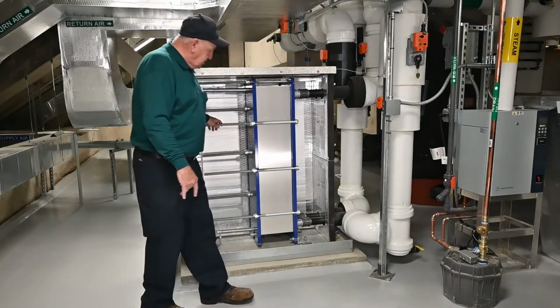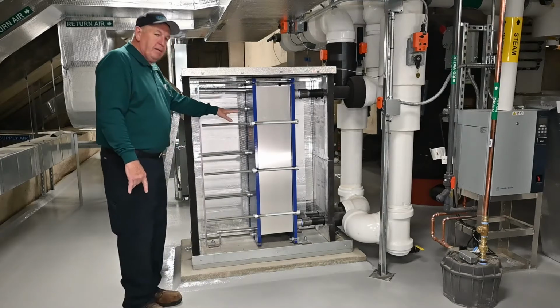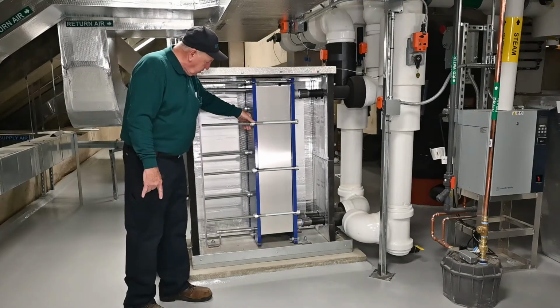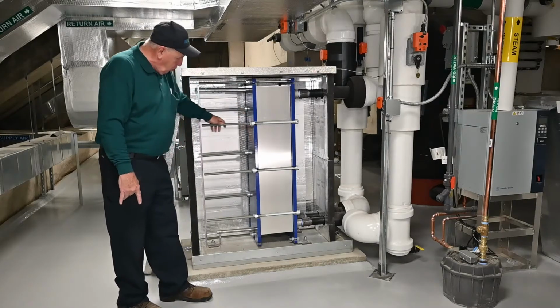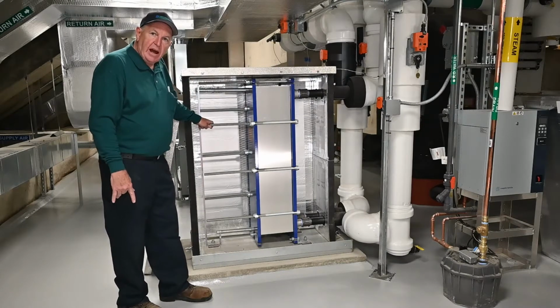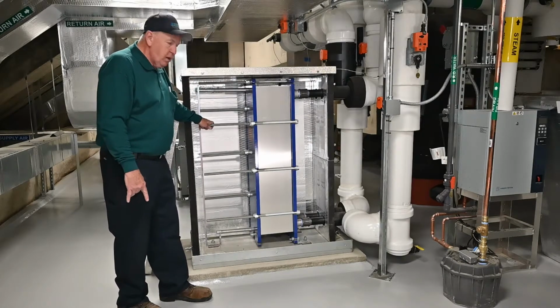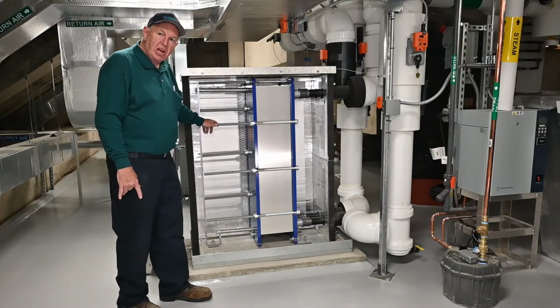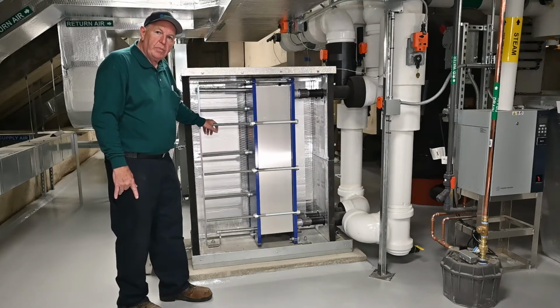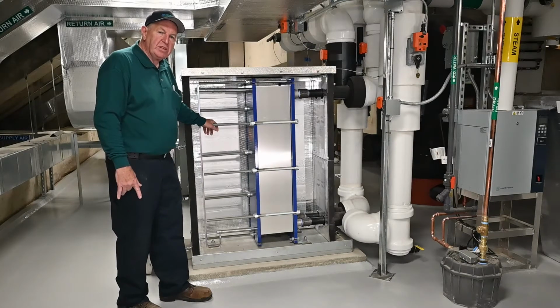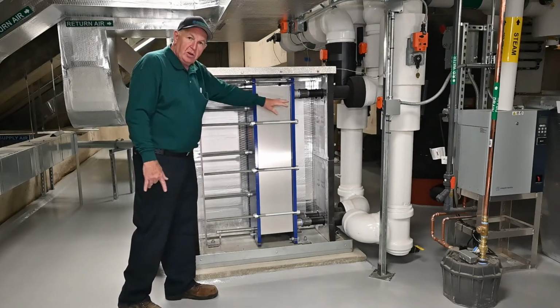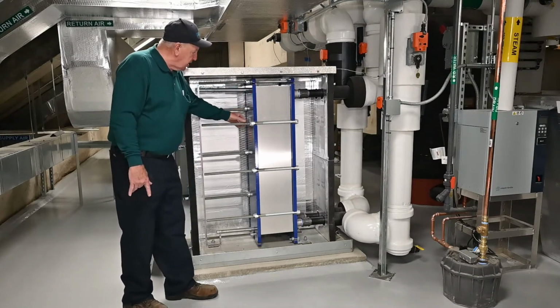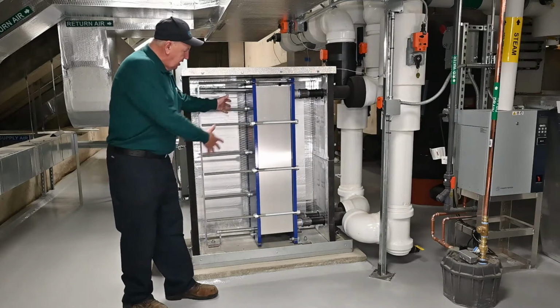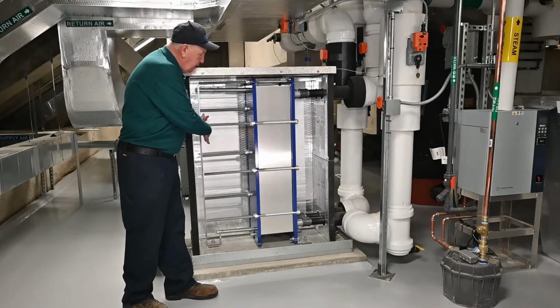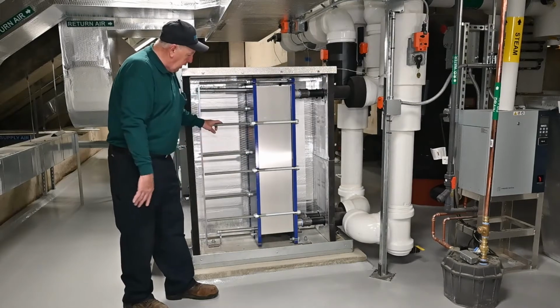And it's an Alfa Laval heat exchanger. It's the reason they leave these rods long is to clean it out. It's a plate and frame heat exchanger. So when it gets plugged, you have to service it. You have to take it apart and get new gaskets in there. You loosen these nuts and you slide the plates apart to clean them.